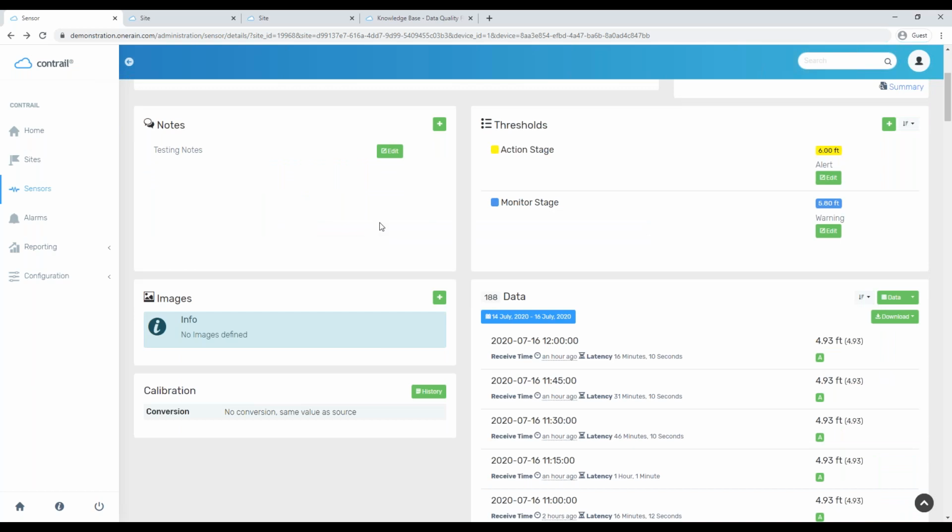So we've talked about that first step in the form that we take for getting from raw to finished data, and that's applying that conversion after it's received as raw data and then it becomes finished data. And then after all of that, there will be an automatic validation process that is applied to each individual data point as it is received into and marked down in the database. Validation is the application of a few different thresholds that are configured by the system administrator.